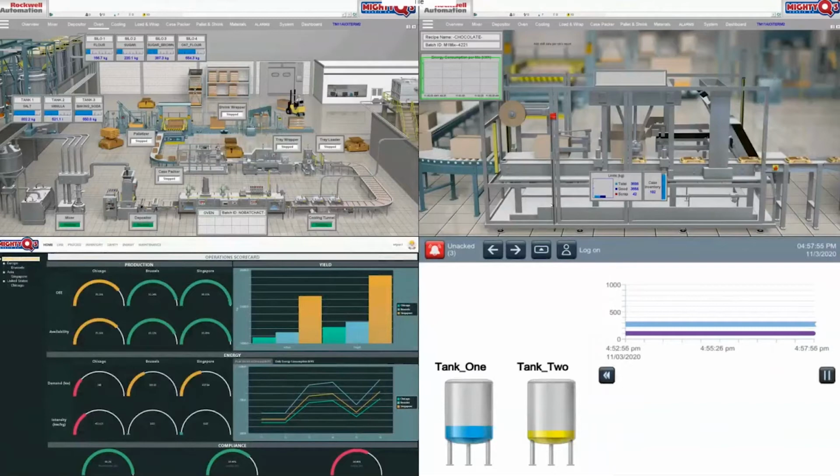ThinManager allows you to do a 5x5 tile grid. So that means you can have up to 25 individual sessions or pieces of content shared on any one monitor or any one screen. And that's very powerful. Some of the drawbacks to tiling, I don't really have control over how this goes. This looks great right now because I threw 4 pieces of content on. If I were to throw a 5th piece on, we're going to wind up with some letterboxing or some black areas of the screen because it won't be able to equally distribute that into a nice sort of breakout on the screen that way.